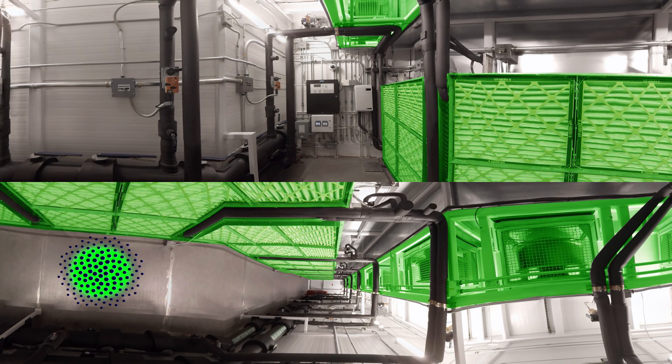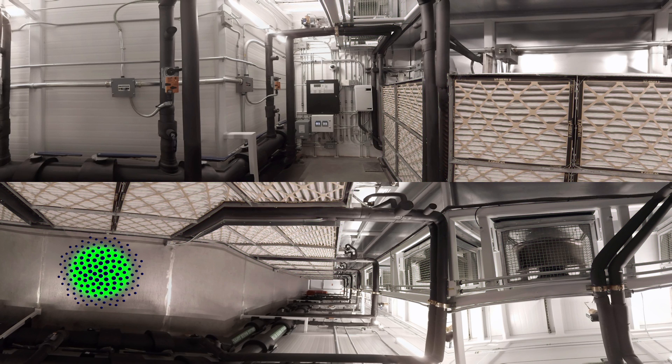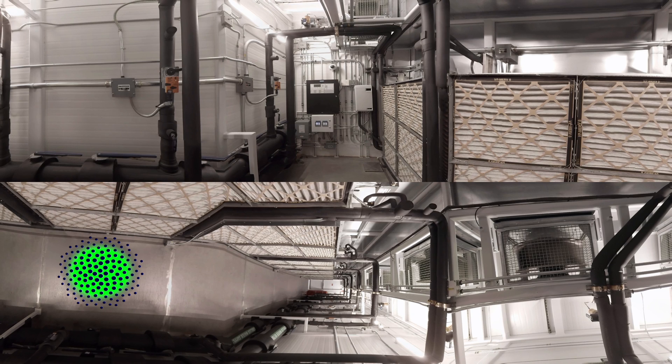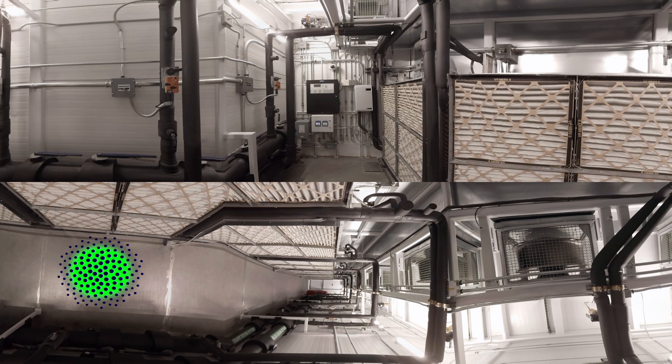From a performance perspective, the cooling block offers multiple cooling configurations, including chilled water, direct outside air with backup trim options, even indirect outside air. In total, this enterprise-level design can cool 500 kilowatts all the way up to a megawatt of IT capacity within a single cooling block.